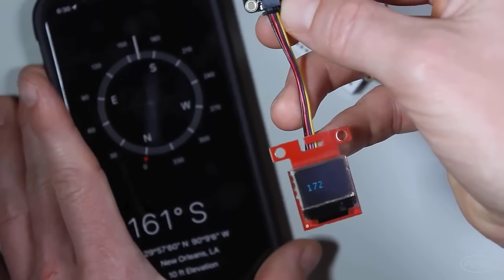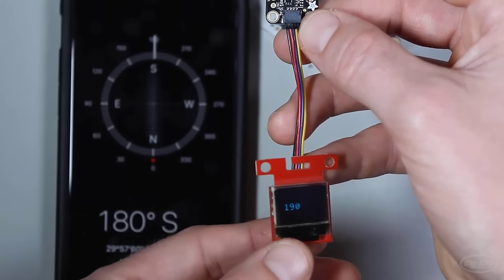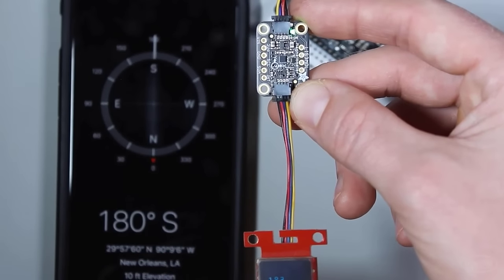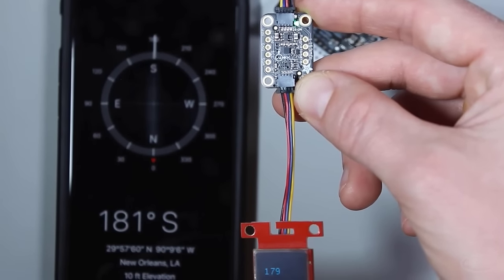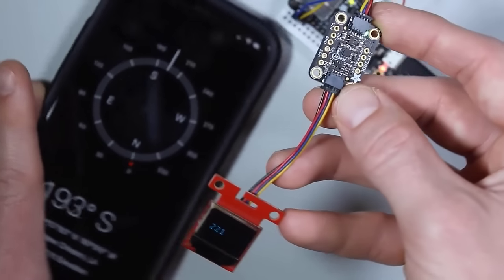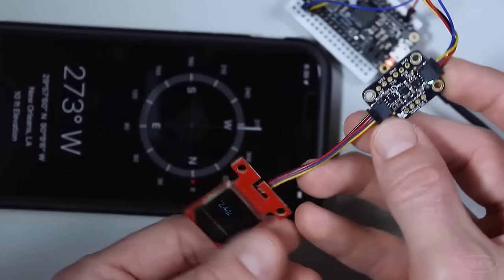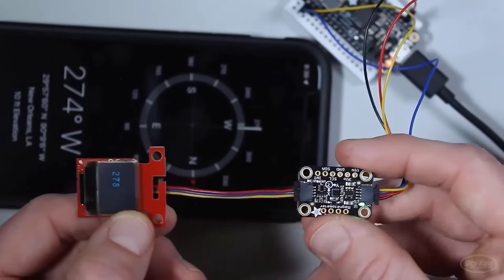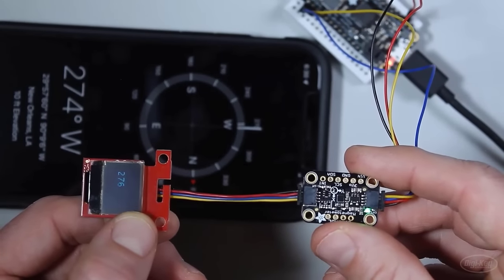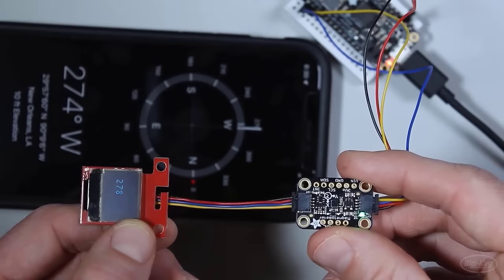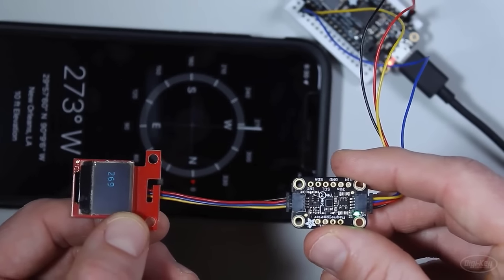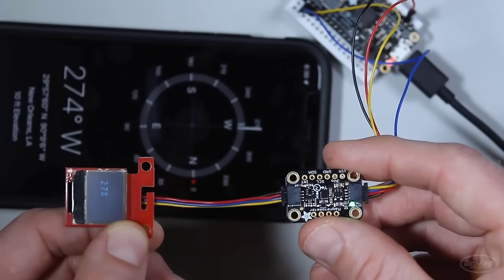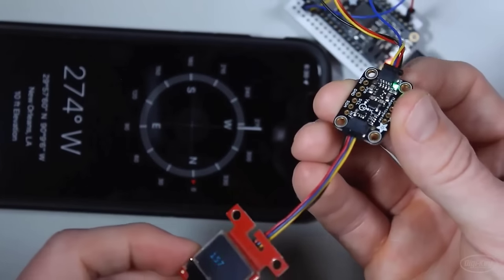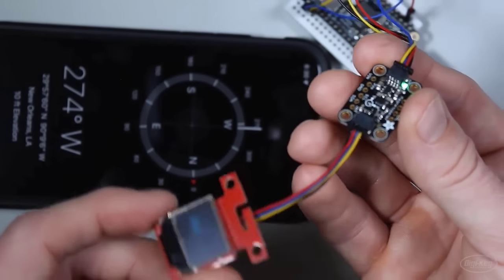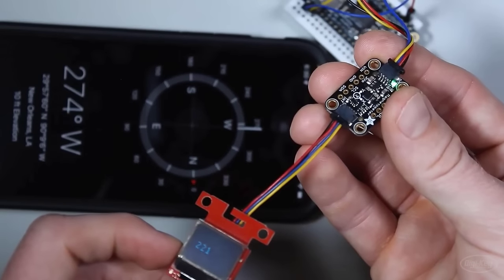Let's rotate my phone a little bit and see if it keeps up. So we'll point it directly south and make sure it's level with the ground. And sure enough, 180. And we'll keep rotating. You can see the compass moving there. 173 is about this way. And it's not going to necessarily be exact, but it's pretty close. Once again, it depends on how parallel I'm keeping this thing to the ground. Hopefully this gives you a start. Remember that wherever you install this, you will need to rerun your calibration and update the settings in your program.